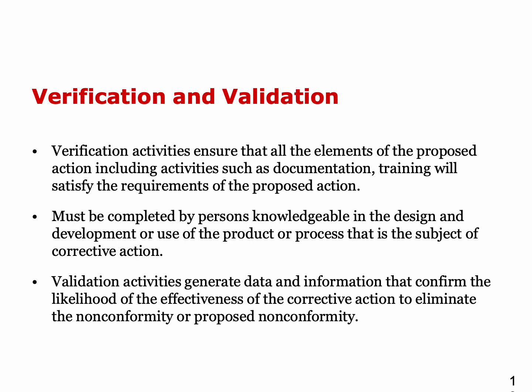Now, when we are, again, having some type of non-conformity, if the non-conformity is because of an equipment deficiency, for example, we will need to verify the activities, we'll need to repair the equipment, but we don't use the equipment unless the repaired equipment is validated. So we will have to go over each and every function of that equipment. We check them through a checklist.